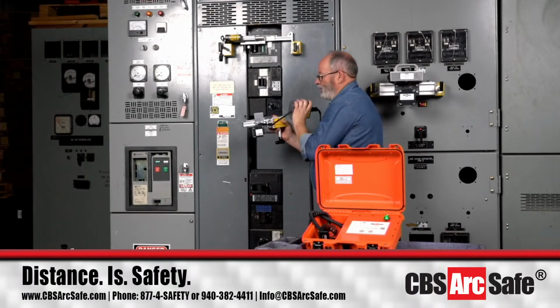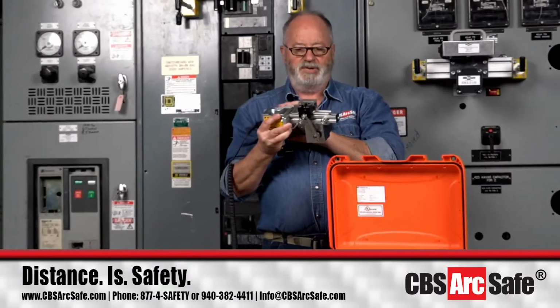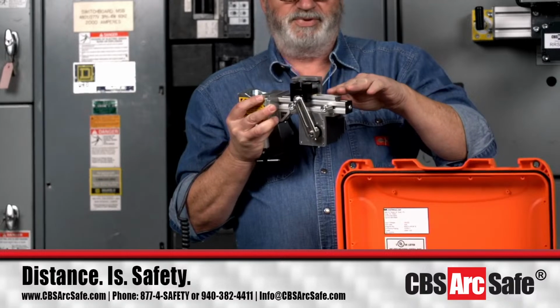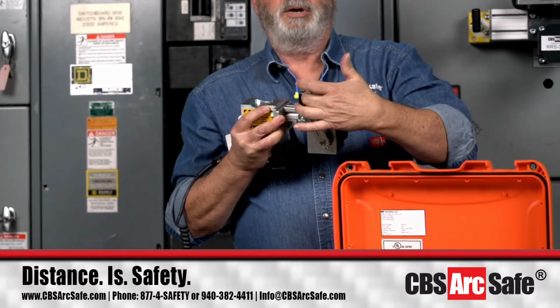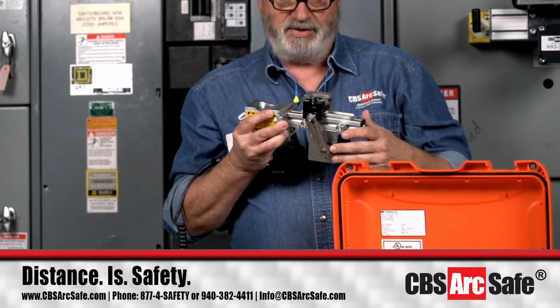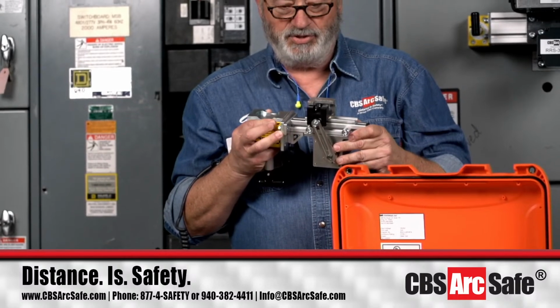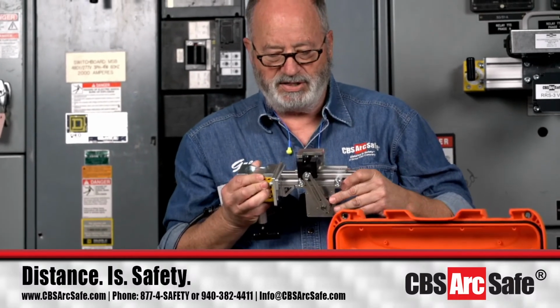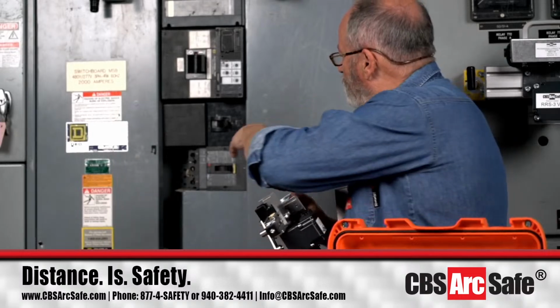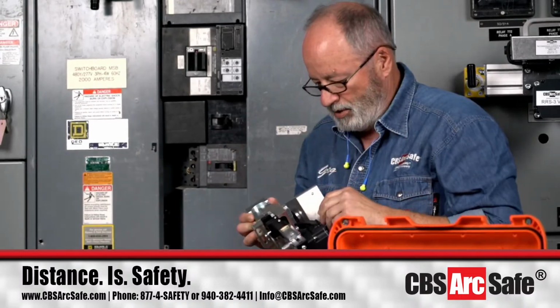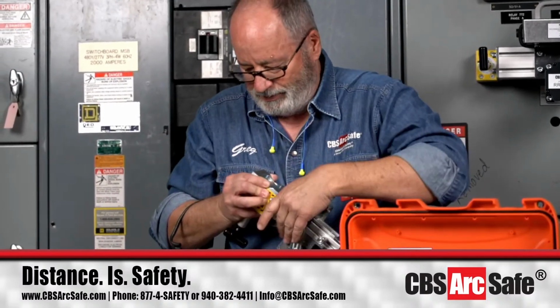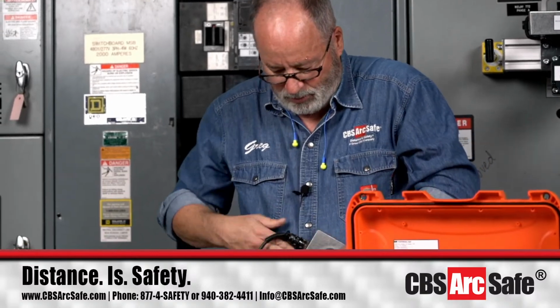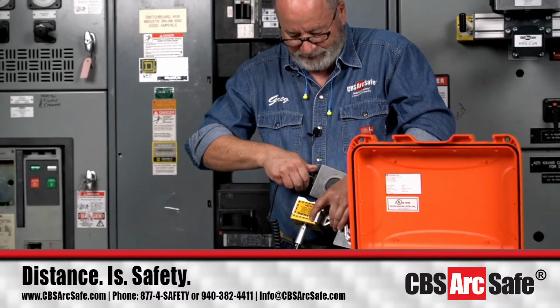You can see it's mounted like this, where this is the flush part with the face of the switchgear up here, but the breaker itself is recessed about 1.5 inches back from the face of the switchgear. That's the reason it has to be built like this, to reach that face. You can see that now with this operation. Let me take this apart real quick and we will get on to the next thing.